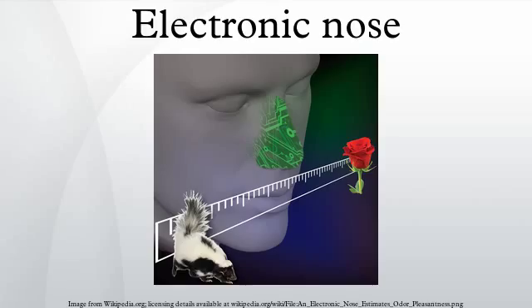Electronic noses include three major parts: a sample delivery system, a detection system, and a computing system. The sample delivery system enables the generation of the headspace of a sample, which is the fraction analyzed. The system then injects this headspace into the detection system of the electronic nose. The sample delivery system is essential to guarantee constant operating conditions.